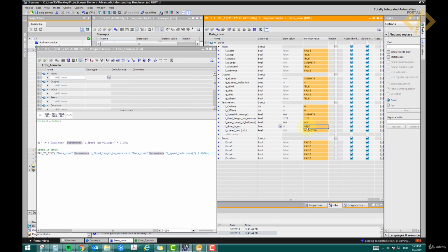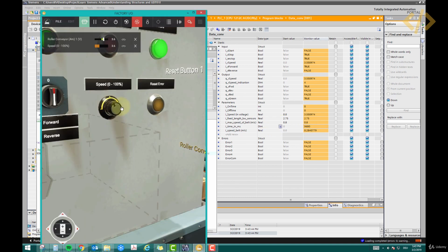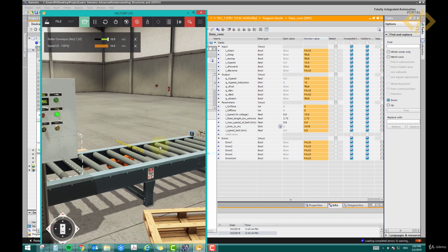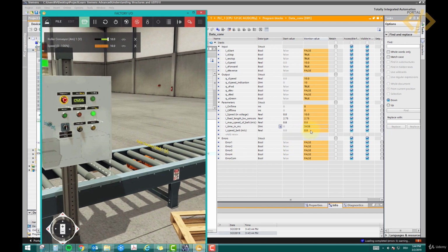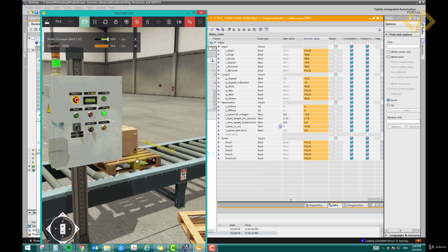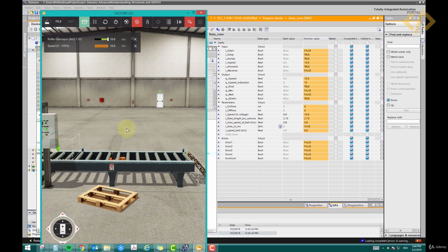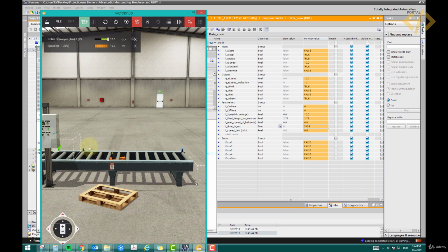Okay, now we have the time approximately 10 seconds at the speed which is 36%. So if I increase it, you can see the time will reduce because now the speed is more. So at 100% speed, it expects the box to reach from one position to another in 3.4 seconds. And if you have a timer in your hand, you can calculate the time, which will be more or less equivalent to 3.438 seconds.